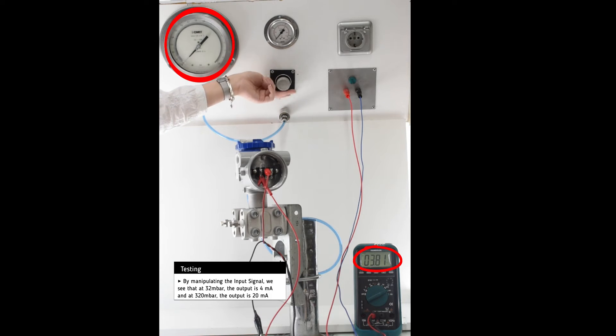By manipulating the input signal, we see that the unit reacts accordingly and at 0.032 bar the output is 4 milliamps, and at 0.32 bar the output is 20 milliamps.